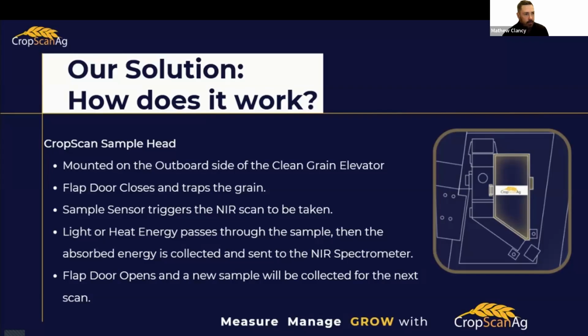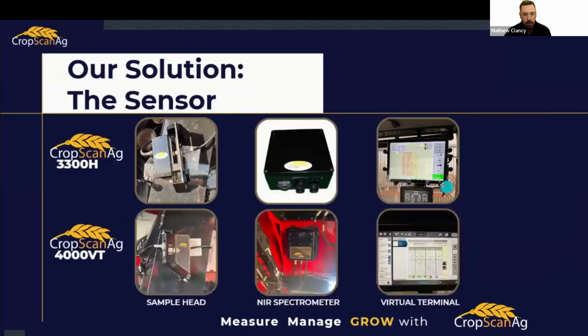If the probe was all the way out, and what I mean is the probe is the fiber that will go back and in, these probes here have the ability to slide in and out. That's basically managing the energy throughput through the lenses. So if we're too far out and we've got canola in the chamber, what do you think is going to happen? The light energy going through the grain is going to be zero at certain parts on the camera. It doesn't really like to multiply something by a zero or negative number, so you're really measuring nothing. If you put crap in, you're going to get crap out.